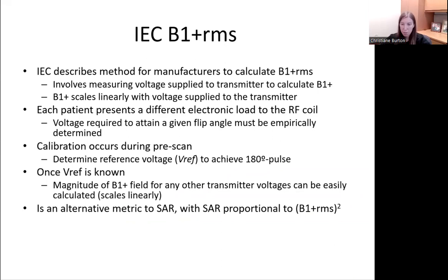SAR is directly proportional to B1 plus squared. The advantage of using B1 plus RMS over SAR is that B1 plus RMS can be directly calculated by measuring transmitter voltages producing the incident RF irradiation. Because B1 plus RMS only depends on the flip angle, it is independent of B naught, the main magnetic field, unlike SAR, which is actually proportional to B naught squared, or the main magnetic field squared.